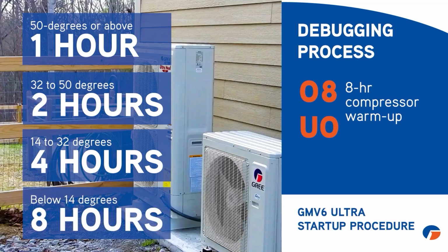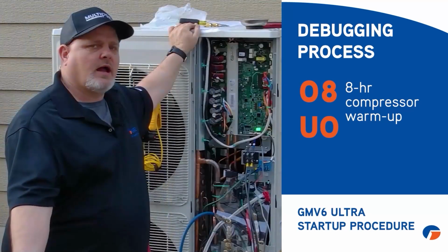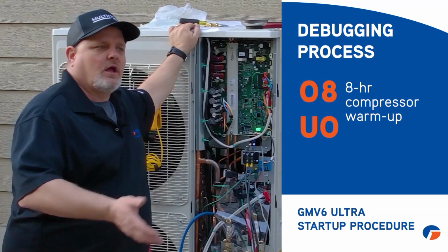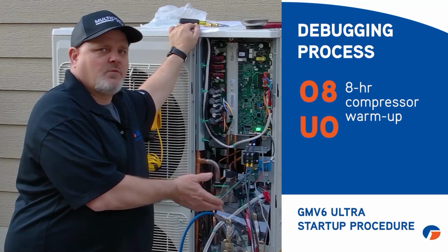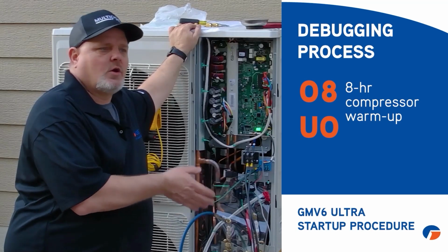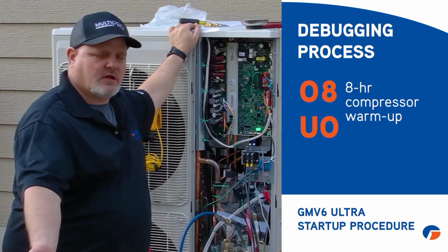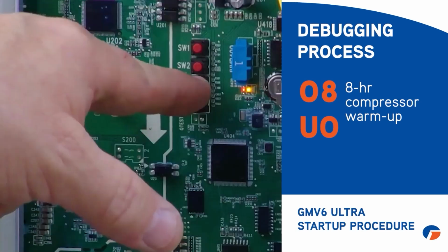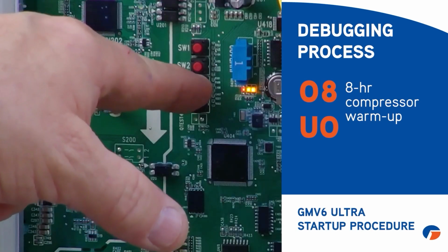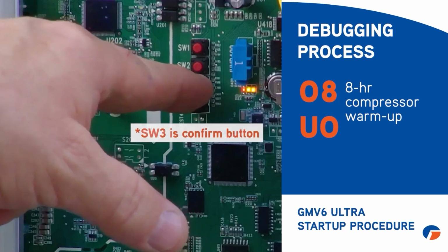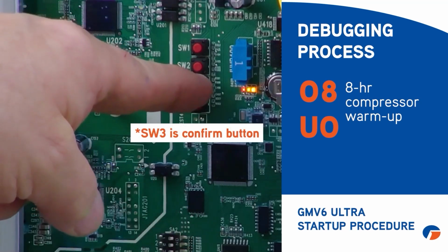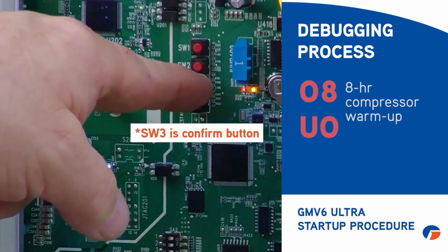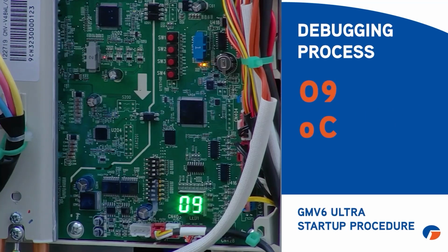And we want to go by the temperature that has been the coldest in the last 24 hours. So if it got down to 0 at night, the night before, and you're going to start that thing up the very next morning and it's 40 degrees, we need to go by that 0 degree temperature. That's what we mean by that. As long as we've reached our warm-up period, you just hit SW3 one time, that'll override it, and it should move on. There it goes, with step 9.